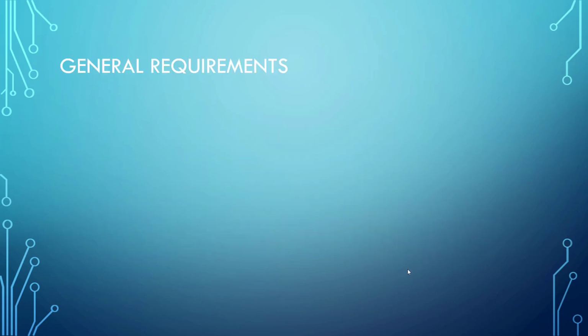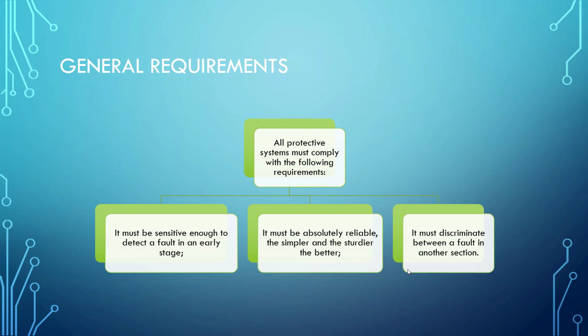All protective systems must comply with the following requirements. It must be sensitive enough to detect a fault in an early stage, because a protective system that is effective enough should be able to trip before the situation escalates. And it must be absolutely reliable. Make it simple and effective. It must also be able to discriminate between a fault in another section, like we said earlier. You have a fire in your high voltage section, your system should discriminate and isolate the other sections.